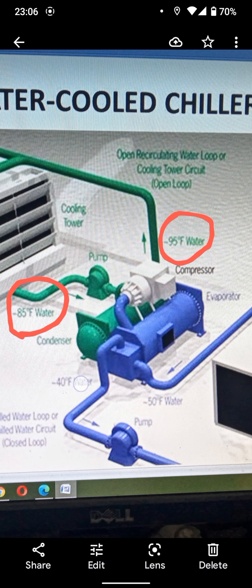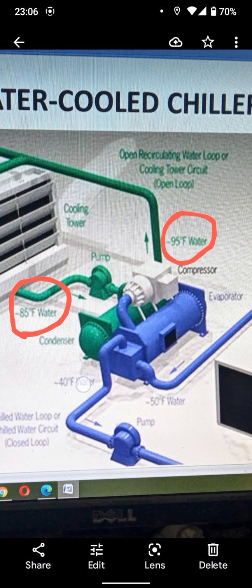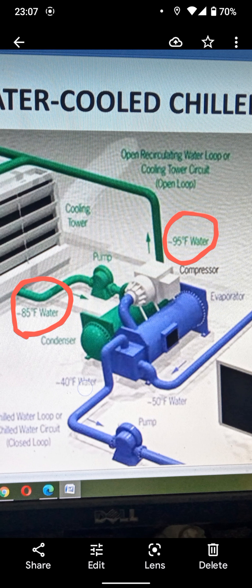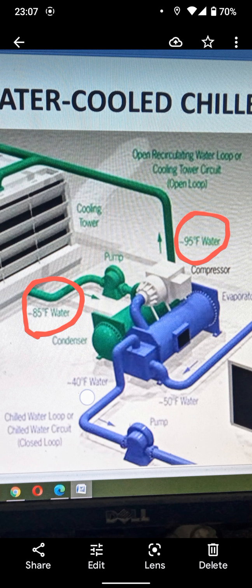But what to do? If you want to run something, they have to provide you the design water temperature, the condenser water temperature. They cannot. How can they? I tell them this cooling tower is on the boundary wall and not getting fresh air.